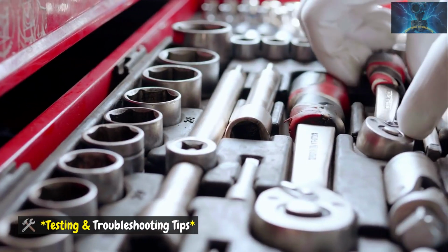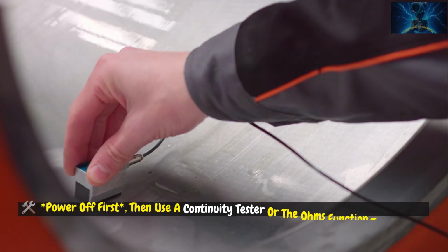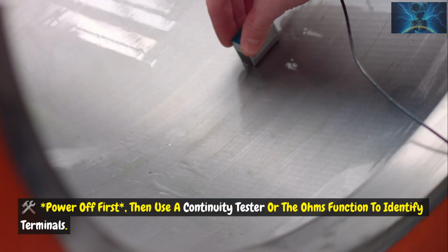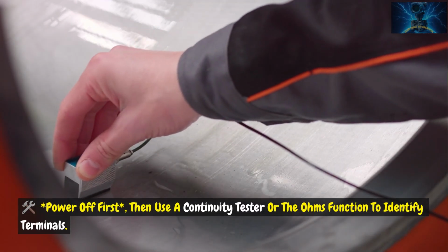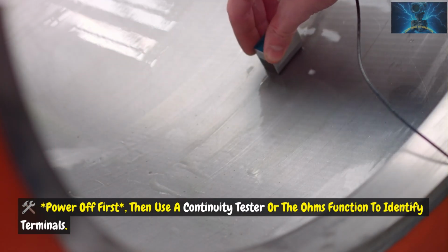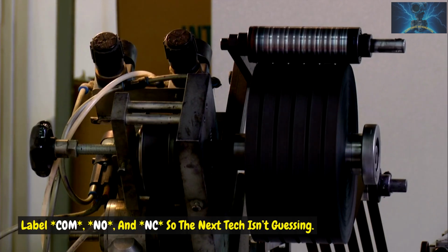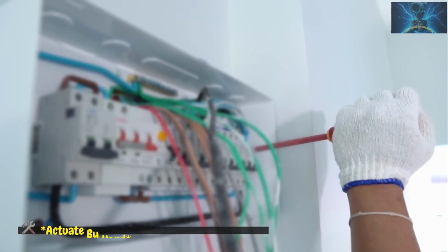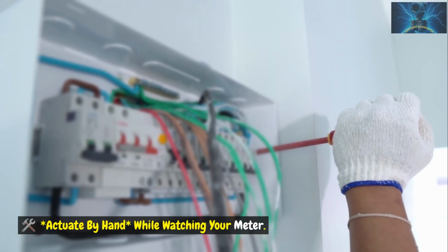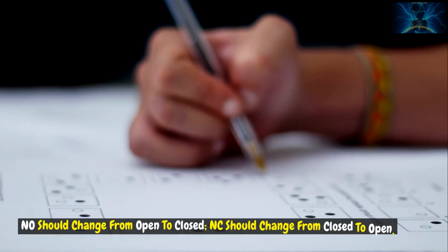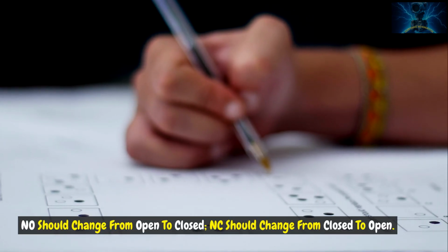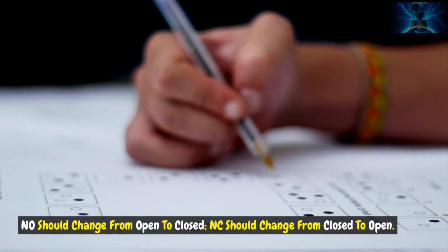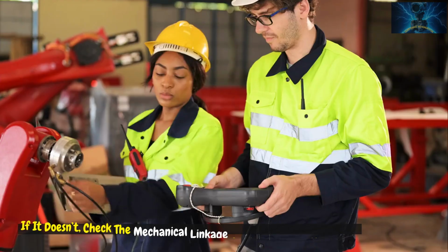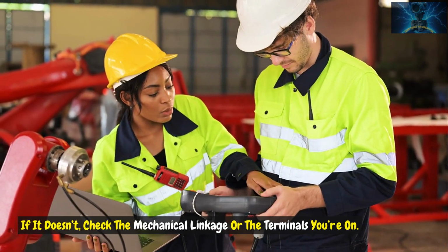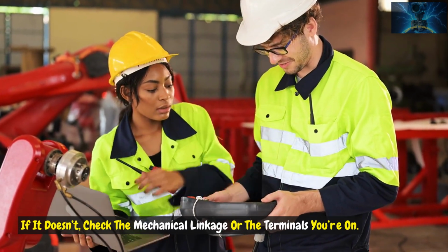Testing and troubleshooting tips. Power off first, then use a continuity tester or the ohms function to identify terminals. Label COM, NO, and NC, so the next tech isn't guessing. Actuate by hand while watching your meter. NO should change from open to closed, NC should change from closed to open. If it doesn't, check the mechanical linkage or the terminals you're on.